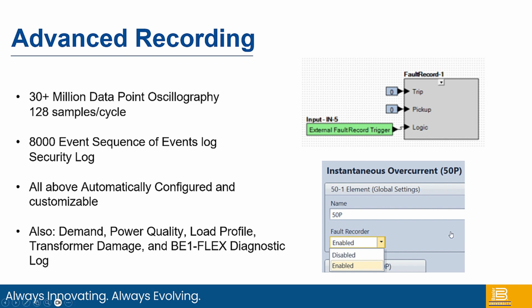Down in the lower right, you see an example of the fault recorder being able to be turned on if you wish. If you want to trigger it with something, let's say a contact input with a GOOSE message or anything like that, you can drive that in logic accordingly. And again, 30 million data point array, and it samples at 128 samples per cycle, which gives you the ability to see harmonics up to the 63rd order. So it's getting very granular in terms of how fast and what it can capture.